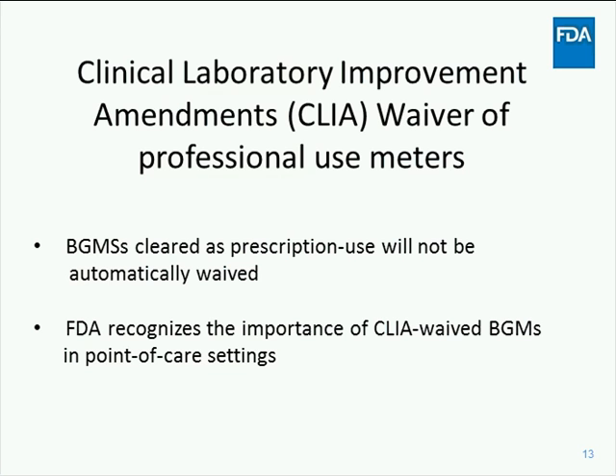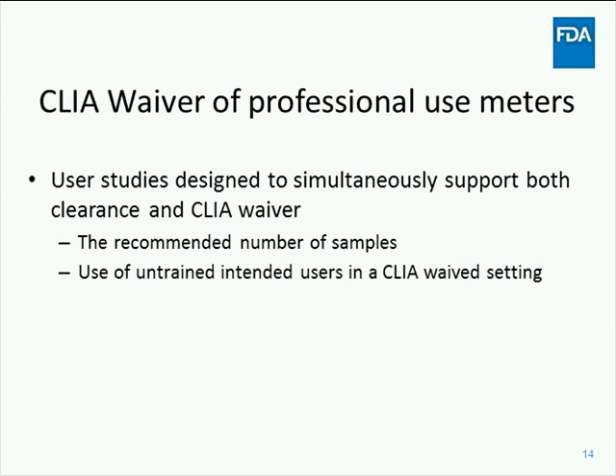However, FDA recognizes the importance of having CLIA waived blood glucose meters in point-of-care professional healthcare settings and intends, through the studies described in this guidance, to facilitate CLIA waiver for these devices. The recommendations in the BGMS guidance, particularly the recommendations for the accuracy user studies, are designed to simultaneously support both clearance and CLIA waiver. For instance, the recommended number of samples and the use of the participants in the study that are representative of the intended CLIA waived users will help to support both clearance and waiver.